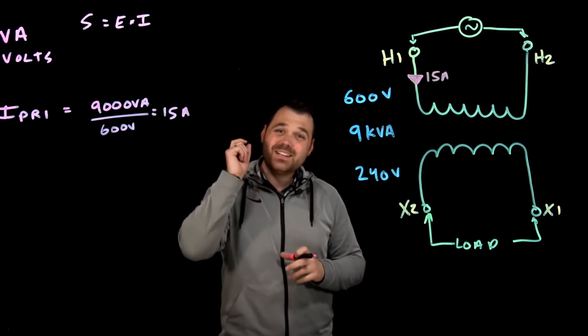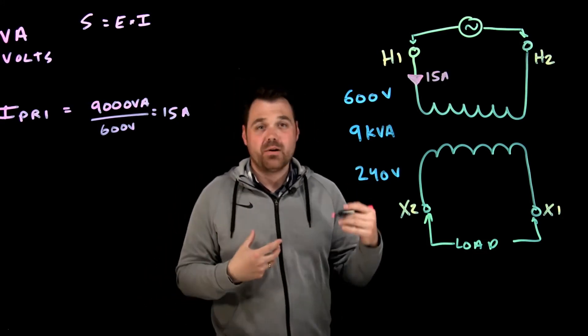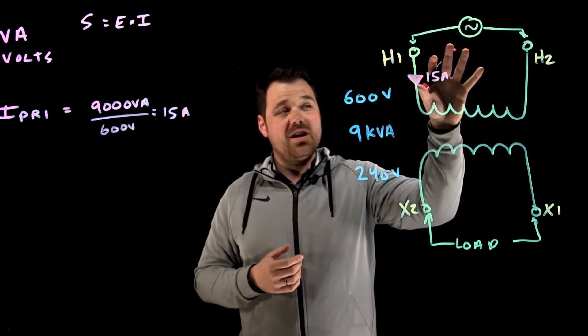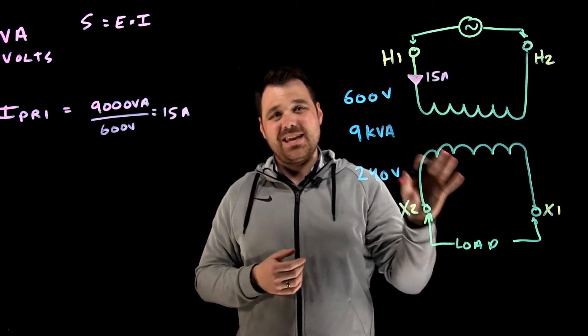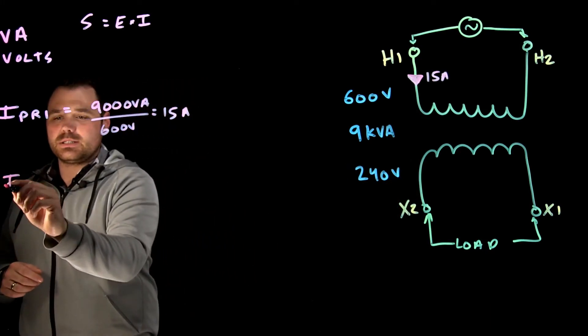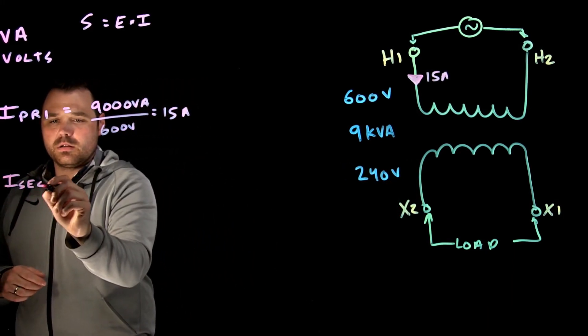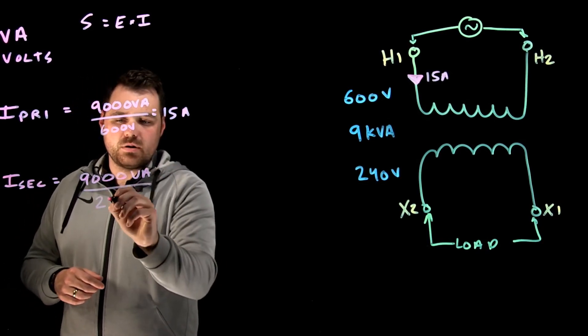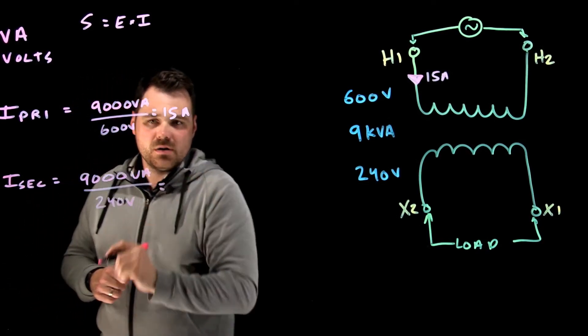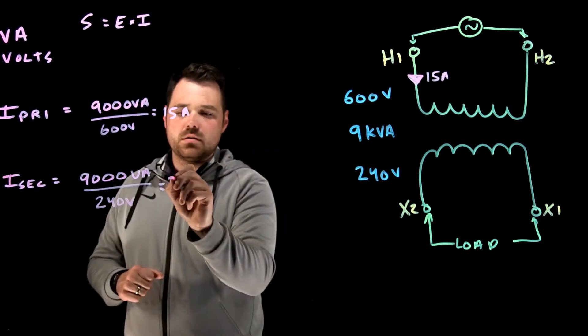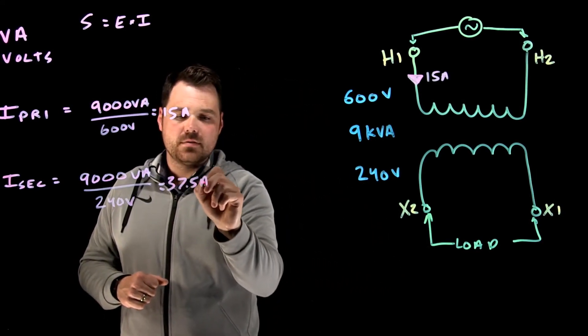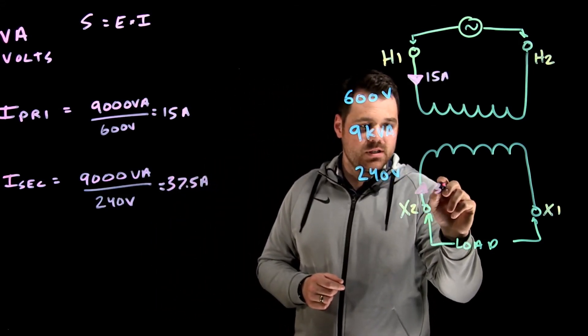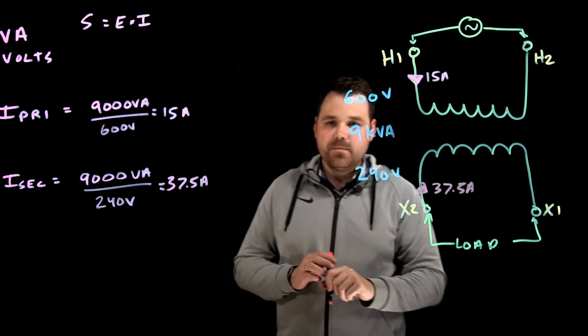I do the exact same thing with my secondary. I know that in a transformer, for basic calculations, my kVA on the primary is the same as my kVA on my secondary. I secondary equals 9,000 VA divided by 240 volts, which gives us 37.5 amps. That will be my secondary current, 37.5 amps.